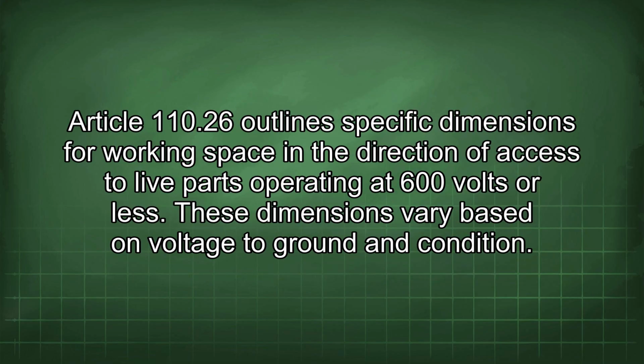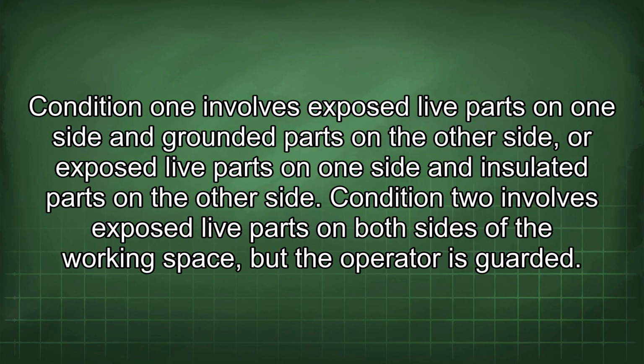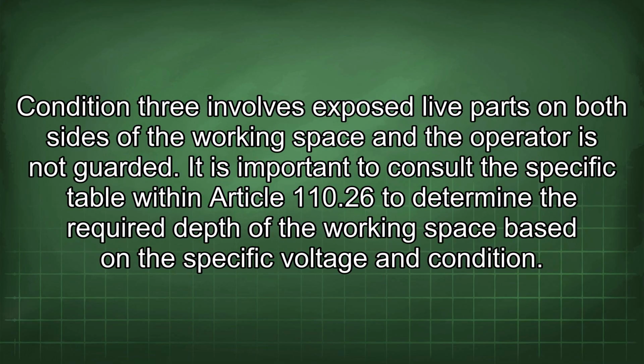Article 110.26 outlines specific dimensions for working space in the direction of access to live parts operating at 600 volts or less. These dimensions vary based on voltage to ground and condition. Condition 1 involves exposed live parts on one side and grounded parts on the other side, or exposed live parts on one side and insulated parts on the other side. Condition 2 involves exposed live parts on both sides of the working space, but the operator is guarded. Condition 3 involves exposed live parts on both sides of the working space and the operator is not guarded.